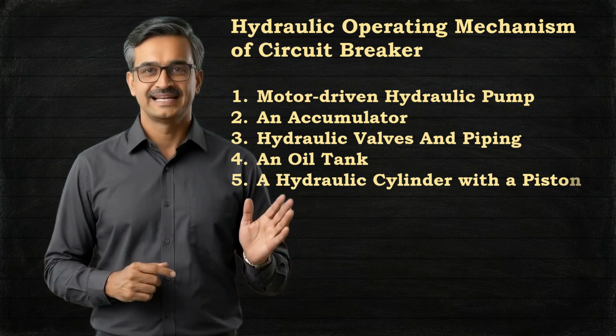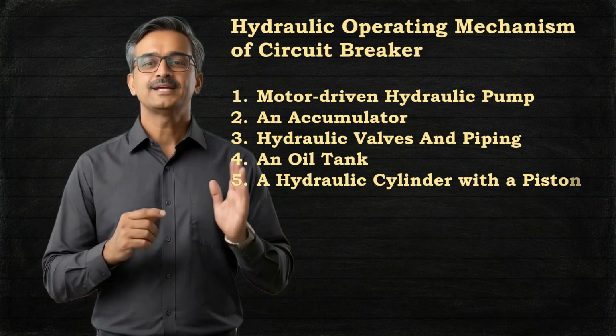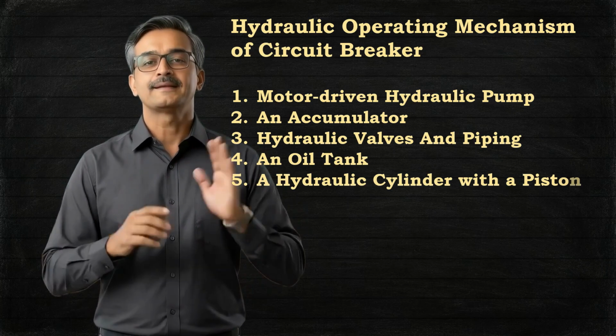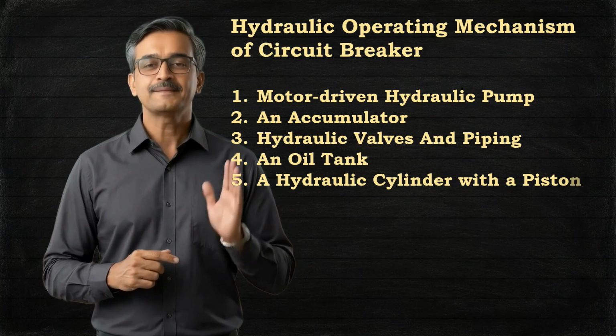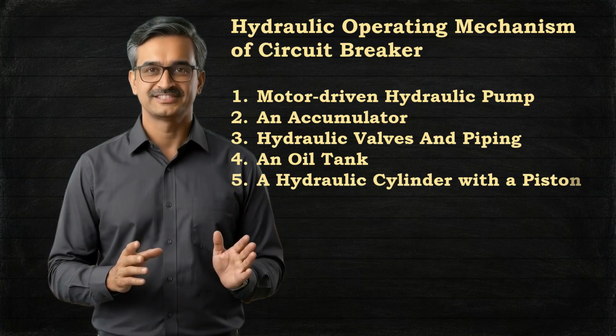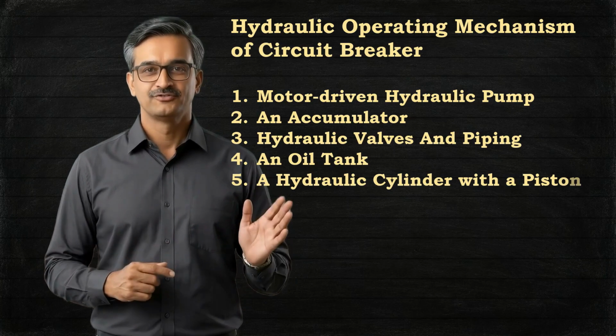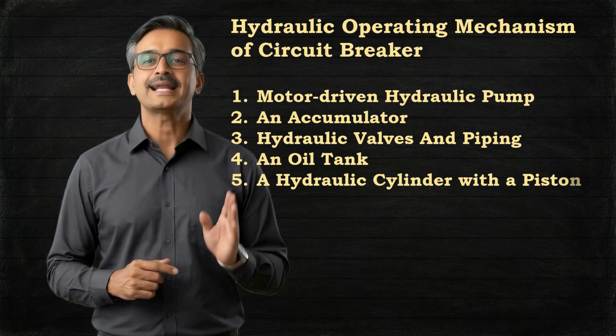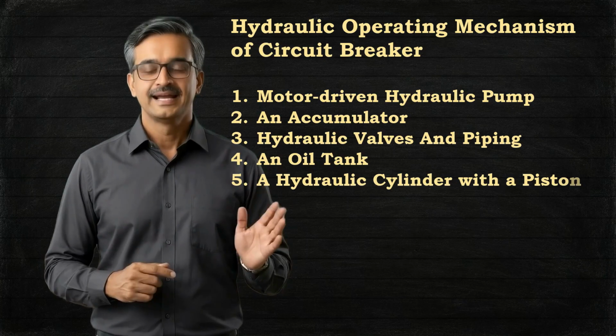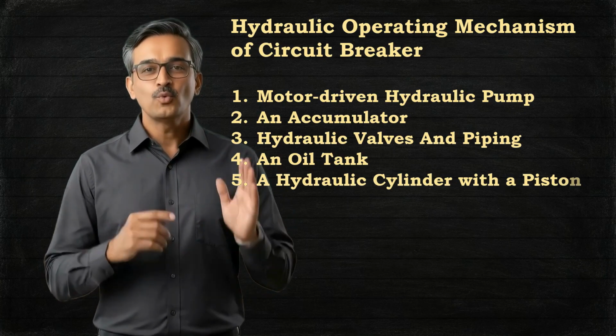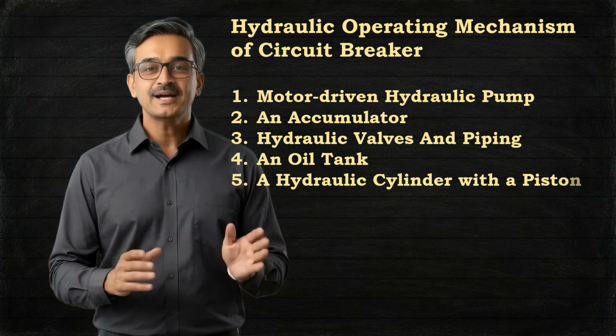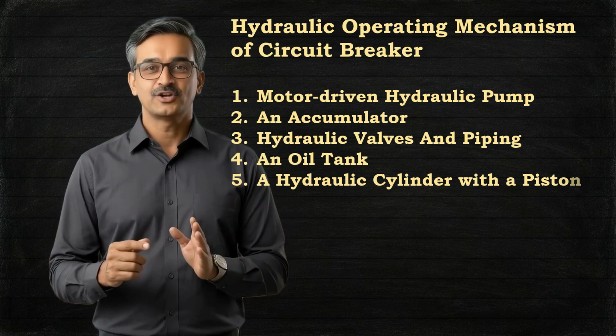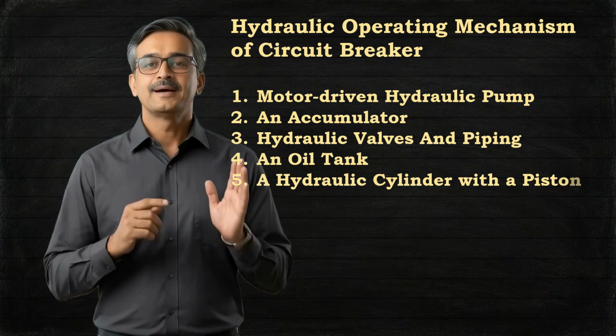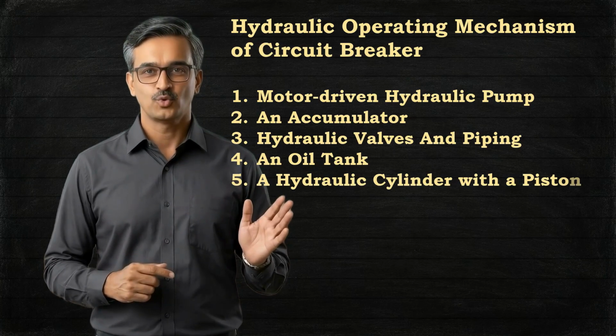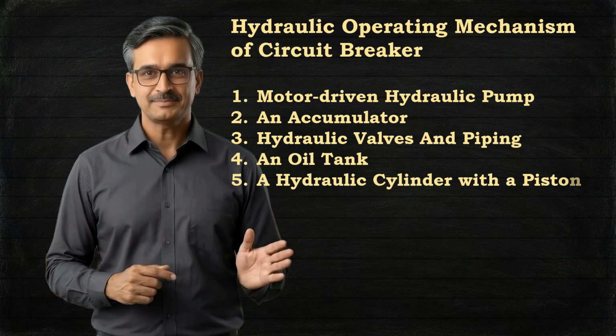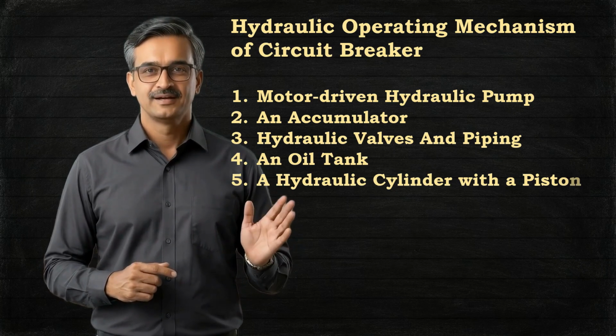When a closing command is given to the closing coil, either from the local or remote control, the hydraulic valve opens. As soon as the valve opens, the high-pressure hydraulic oil flows from the accumulator into the hydraulic cylinder, where it pushes the piston. The movement of this piston is utilized to operate the mechanical links of the closing mechanism of the circuit breaker. As a result, the moving contact travels at high speed and closes the circuit breaker.